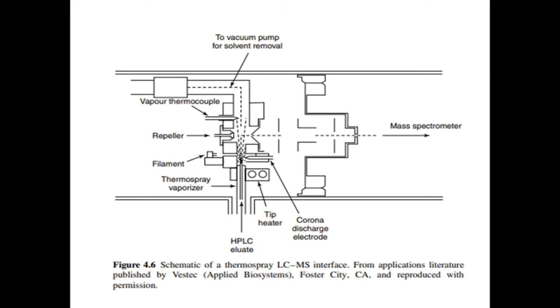The ions formed are then directed through a sampling cone at 90° to the direction of vapor flow to minimize the chances of blocking the entrance into the source of the mass spectrometer, while the vast majority of the vapor generated by the mobile phase is removed by a pump directly opposite the capillary.